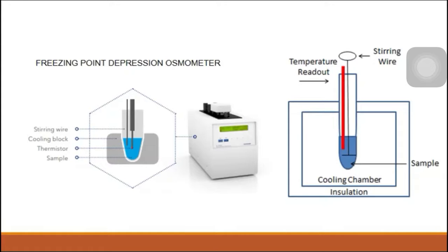This stirring causes the sample to become partially crystallized. The formation of ice crystals causes the release of thermal energy, and the heat generated brings the sample to a temperature that is equal to its freezing point. After a short period of time, an equilibrium is reached where melting and freezing of ice crystals are balanced, and the sample's temperature stays constant.